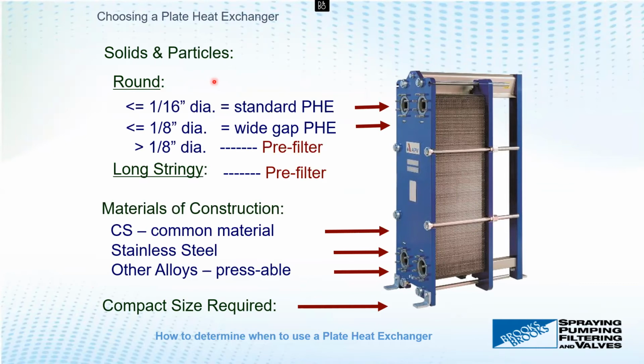Because of the tortuous path and the plate gap, we need to understand what's going on in there. If you have small particles that are nice and round and uniform, typically anything that's 1/16 of an inch or smaller will fit through these gaps no matter what. It'll be super easy, keeping the plate and frame heat exchanger running without fouling or buildup.